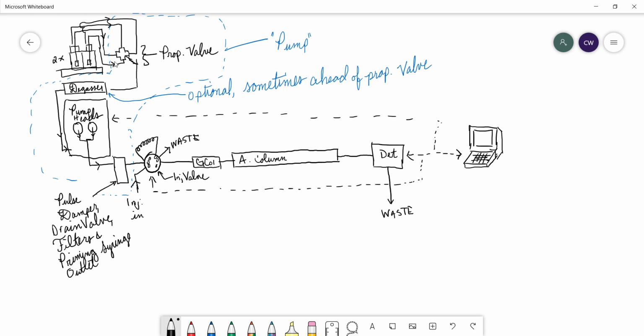Most proportioning valves can have up to 4 mobile phase constituents plumbed in, and that will output to a degasser, or sometimes the degasser isn't there at all, or sometimes the degasser is immediately after the eluent reservoirs before the proportioning valve. Okay, that will then feed into the pump heads, which are designed in the way that I drew from the last video, right? The reciprocating pump heads, and those reciprocating pump heads will output the degassed proportioned mobile phase to the pulse dampener, okay?